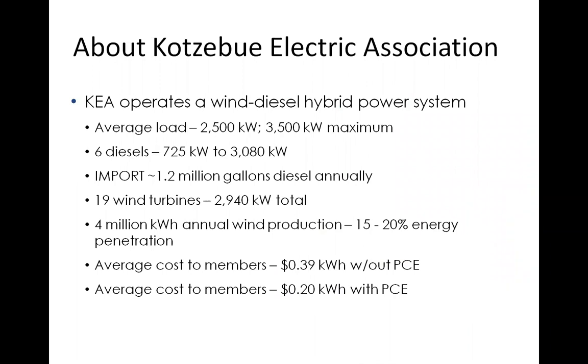We have essentially a wind-diesel hybrid power system here at Kotzebue Electric. Our average load is 2,500 kW, peaking at 3,500 kW in winter, usually around January or February. Our lowest loads are in summer - nighttime in June or July we can get down to close to 1,400 or 1,500 kW. We've got 6 diesel generator sets ranging from 725 kW up to our largest, rated at 3,080 kW continuous. At this point we're importing about 1.2 million gallons of diesel fuel annually to provide electric power for the community.